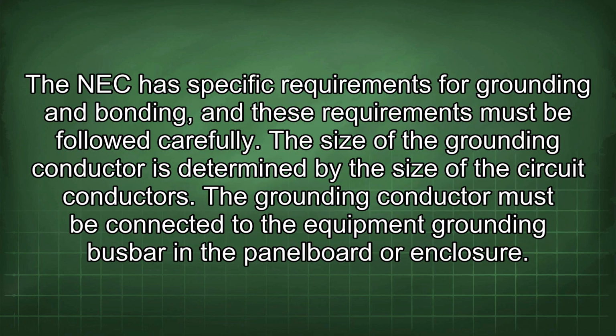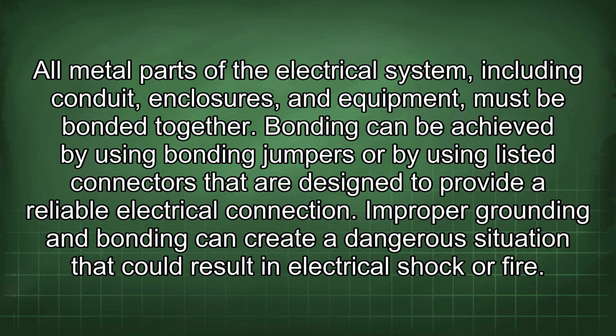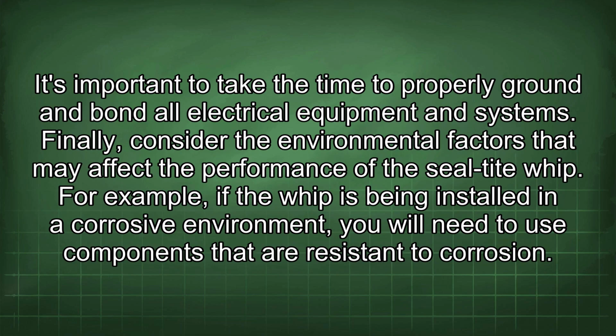The NEC has specific requirements for grounding and bonding, and these requirements must be followed carefully. The size of the grounding conductor is determined by the size of the circuit conductors. The grounding conductor must be connected to the equipment grounding busbar in a panel board or enclosure. All metal parts of the electrical system, including conduit, enclosures, and equipment, must be bonded together. Bonding can be achieved by using bonding jumpers or by using listed connectors that are designed to provide a reliable electrical connection. Improper grounding and bonding can create a dangerous situation that could result in electrical shock or fire. It's important to take the time to properly ground and bond all electrical equipment and systems.